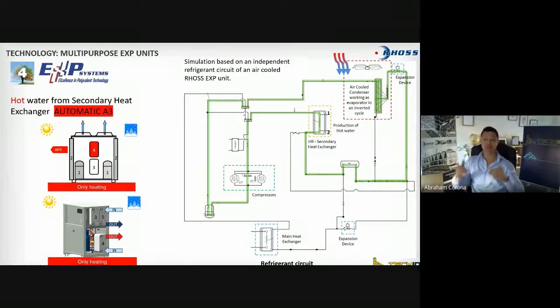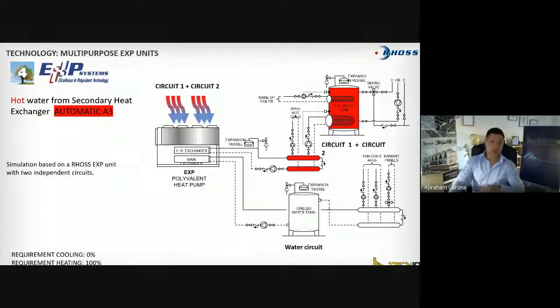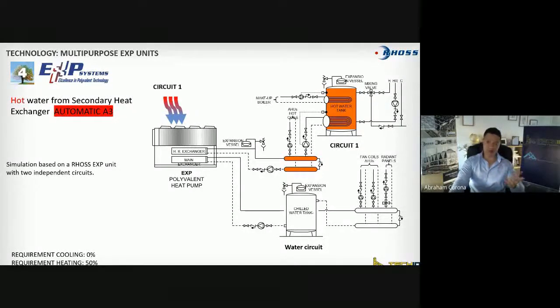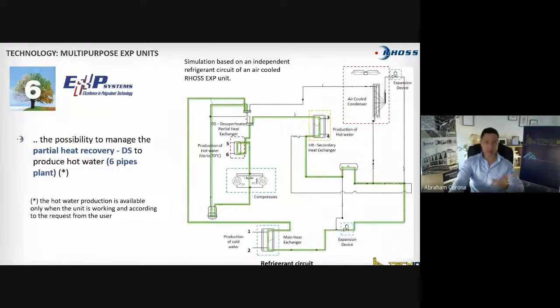And in simple words, this is exactly how you produce in a 4-pipe unit, for only one unit. You can produce only cooling, heating and cooling, and only heating. I think that starts to give you a better idea of where we are producing 2 pipes and 4 pipes. This is how we're looking in the water circuit. At 100% demand of heating, both circuits will be running as heat pumps, reversible cycle, and we're taking heat from the environment to heat the unit. If we only need 50%, we only run one circuit. We have covered what we call the 4-pipe system, all right?